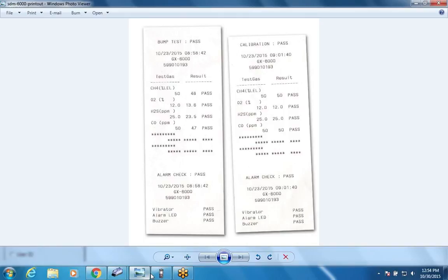Once I hit it, it'll stay on this screen until I hit end, whether I do a bump or a calibration, and then it'll go back to the home screen, ready to do something else. If it passes the calibration, it'll reset the calendar. If say the vibrator fails, it's still going to pass the calibration and update the date and time.